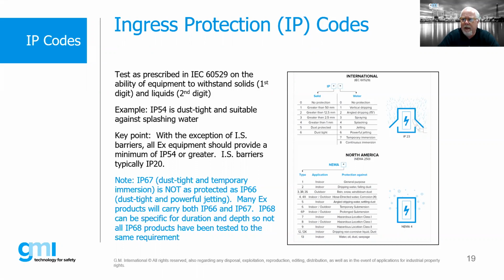The second digit applies to water ingress. So generally speaking, as we go up higher in the numbers, if you will, it's a higher level of protection. Generally speaking, EX equipment must maintain an IP54 or greater. So a lot of EX equipment that you will find out there will be dust tight, which they'll be IP6, and they'll also be suitable for direct water applications such as either jetting, powerful jetting, or temporary immersion. So 65, 66, 67, and in some cases 68.